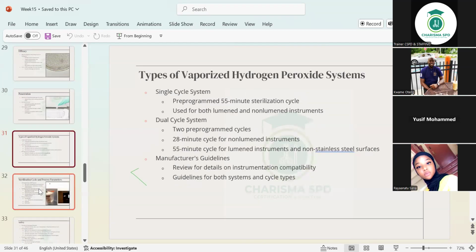Talking of the types of vaporized hydrogen peroxide systems, which you don't need, but the point is you just need to know about it. They have the single cycle system, the dual cycle system, and the manufacturer's guidelines is the primary thing for you. Whether you're using the single system, it's pre-programmed for 55 minutes, used for both lumen and non-lumen instruments. The dual cycle is two programmable cycles, the 28 cycle and then the 55 cycle. It's up to you when you get to your job, and that's what they have. That's it. Don't be surprised that one has two cycles and one has one.